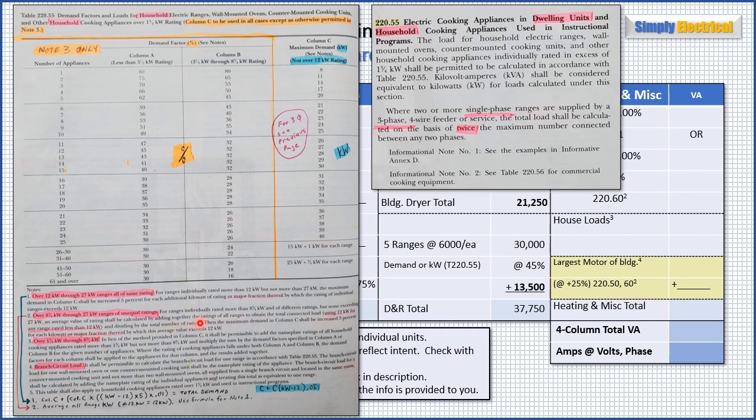Okay, we'll stop right there for a sec. All that's saying is you're averaging. You're taking the averages. So again, I have another formula down here, or instructions, for number 2, and it says average all your range kWs, but you've got to make sure that for any kW that's under 12 kW, you use 12 kW as the value. So you can't use any values less than 12 kW. Anything below that is automatically used as 12 kW.